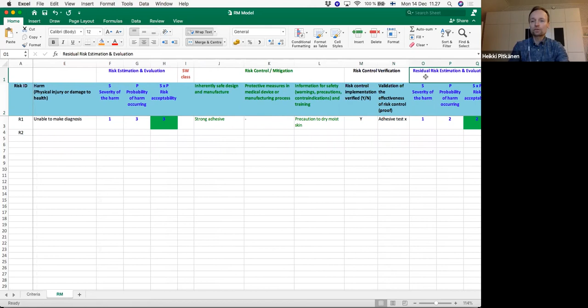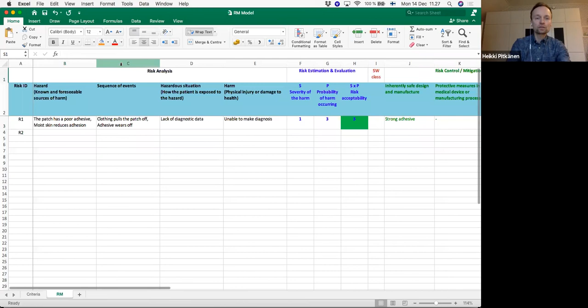It begins from planning, and figuring out severities and probabilities in advance is what you need to do. So you set up the acceptability levels and what is considered unacceptable before you start then assessing your risks. And I will come back to this, but then the sequence of events would flow through the hazards and hazard situations and the harms, through the mitigations for the product and risk control verification, any residual risks that remain after the mitigation, and some additional considerations.